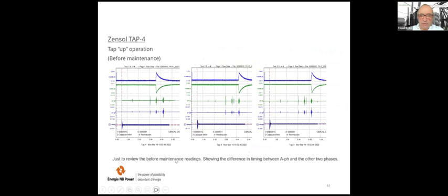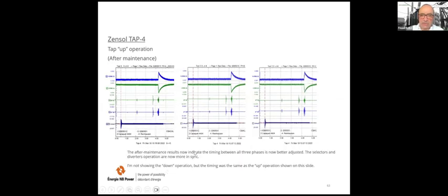So just to review, the before maintenance reading showing the difference in timing between A phase and the other two phases. So it was the first, the before maintenance. And now the after maintenance results indicate the timing between all three phases is now better adjusted, and the selectors and diverter operations are now more in synchronization. I'm not showing the down operation, but the timing was the same as the up operation shown on this slide. So now they are perfectly adjusted. So it's why Vibroacoustic is really, in the beginning, what kind of benefits the Vibroacoustic brings to utilities. The timing and the mechanical adjustment were highlighted.